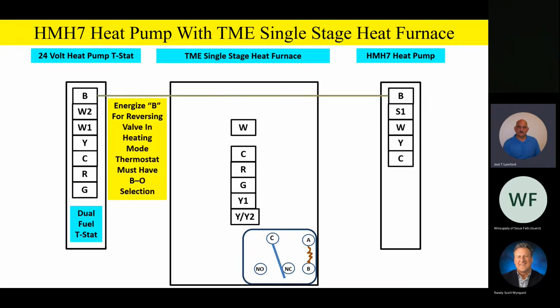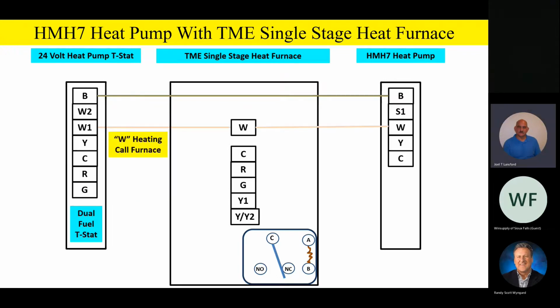So B terminal is going to go outside for reversing valve operation in the heating mode, just like we had before. W1 from the thermostat, or W from the thermostat if you just have a single stage heat thermostat or a single stage auxiliary heat thermostat, W1 will go out to W on the furnace, and that'll go outside for defrost mode whenever we call for defrost. We're going to bring the furnace on during defrost.